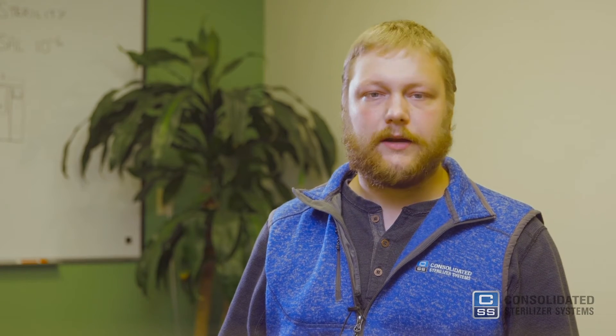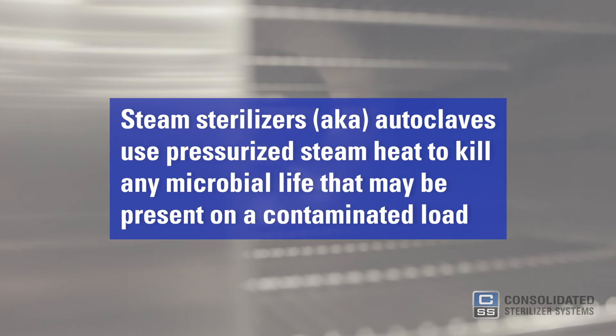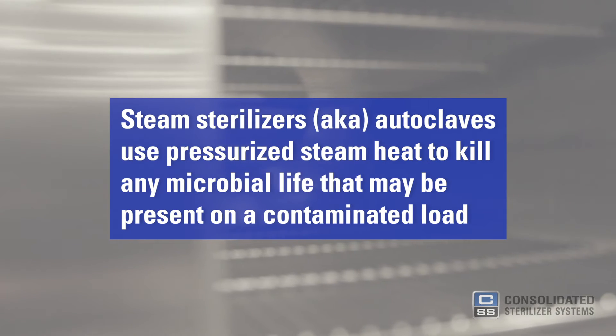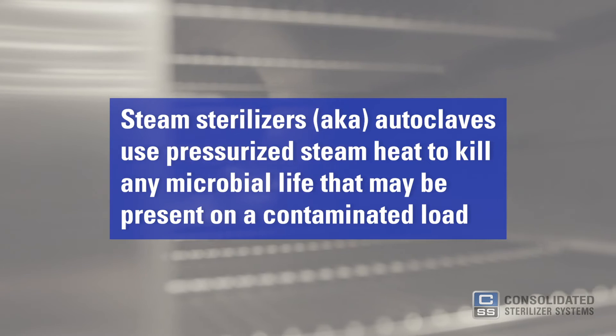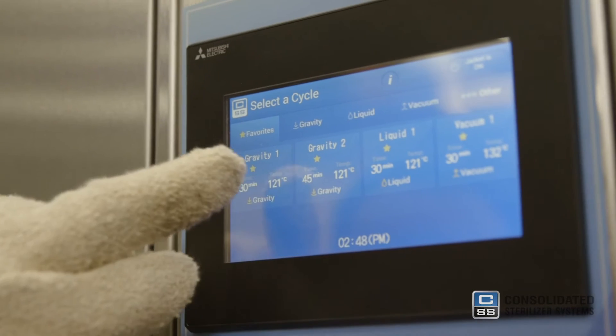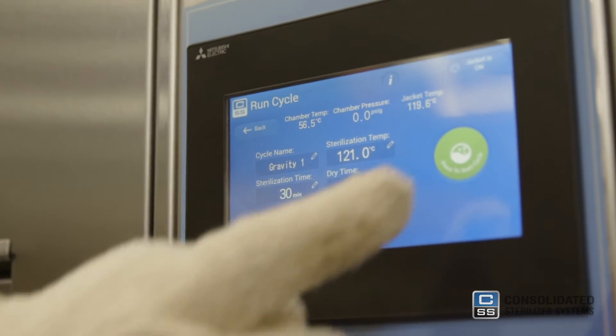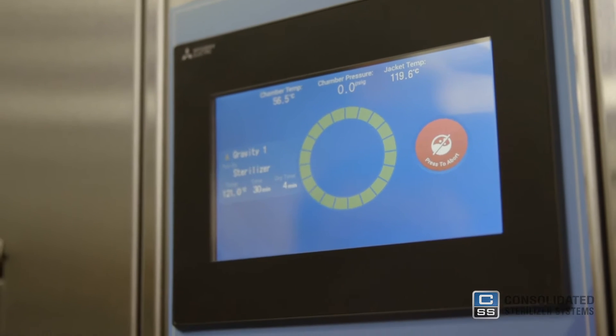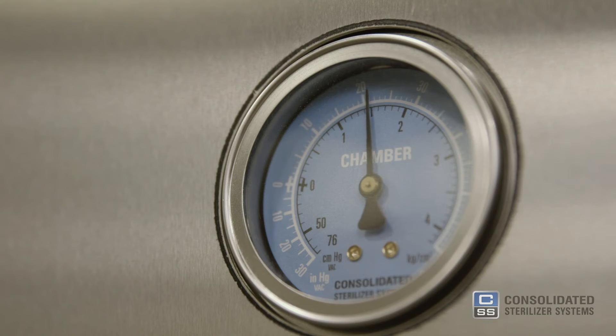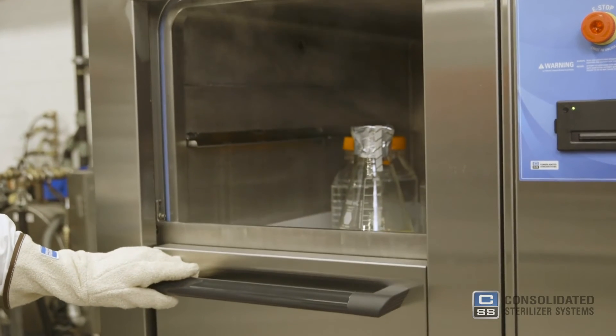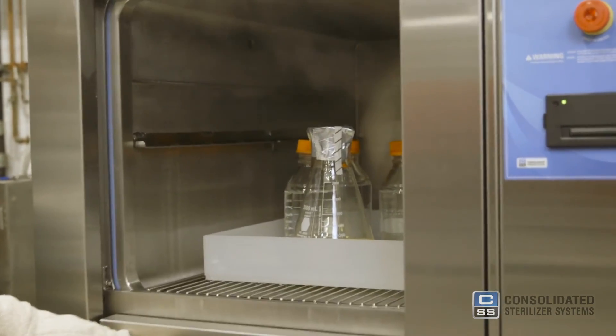Now let's talk about how steam sterilizers work. Steam sterilizers, also known as autoclaves, use pressurized steam heat to kill any microbial life that may be present on a contaminated load. Autoclaves both large and small operate using the same principles as your common kitchen pressure cooker. The door is locked to form a sealed chamber and all air within that chamber is replaced with steam. The steam is pressurized to achieve sterilization. Once a cycle is complete, the steam is exhausted and goods can be removed.